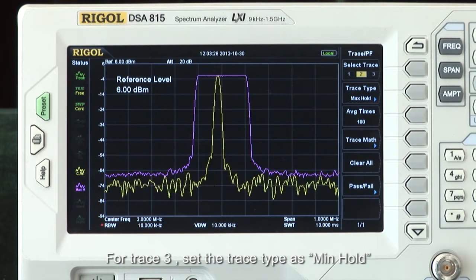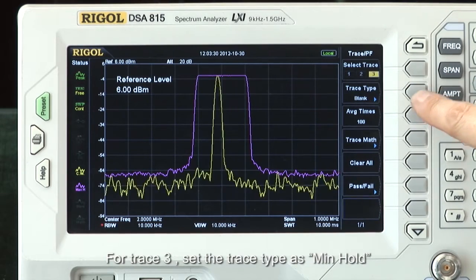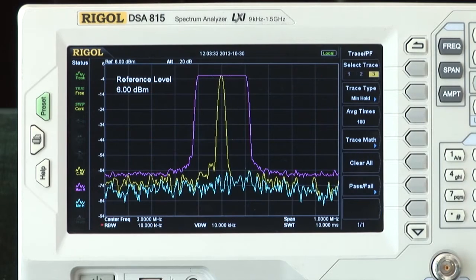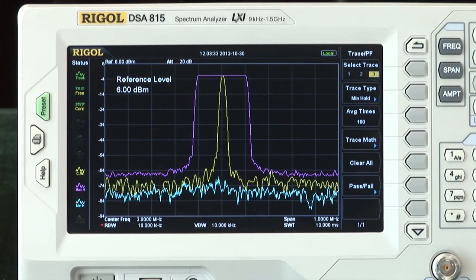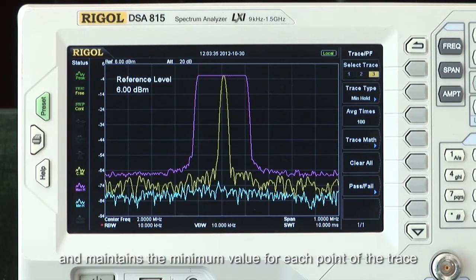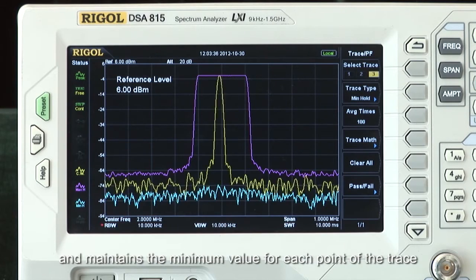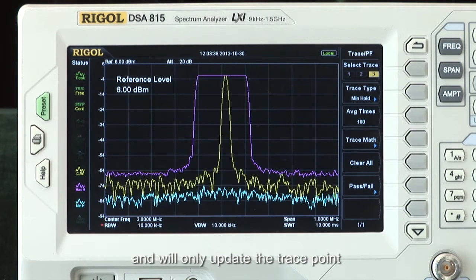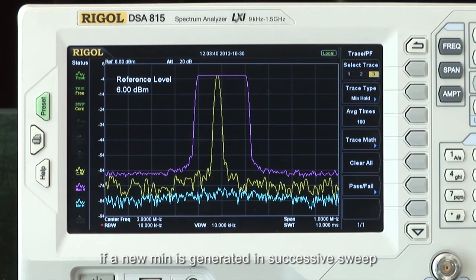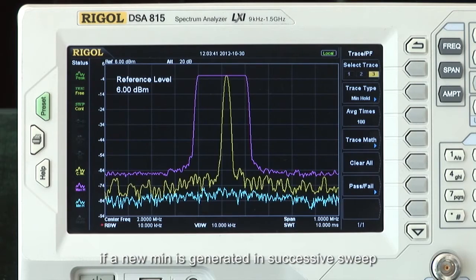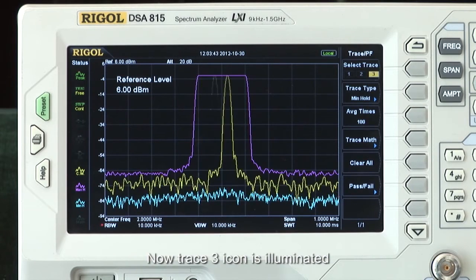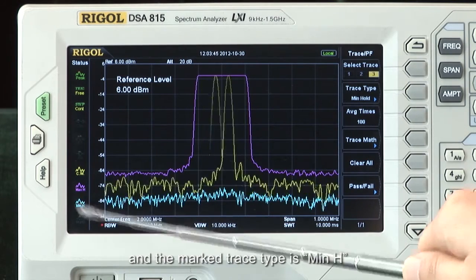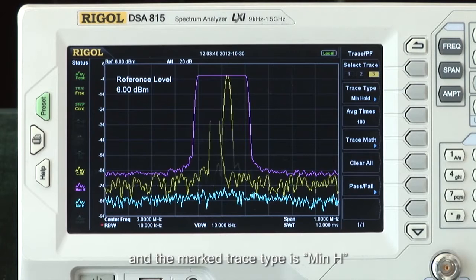For Trace 3, set the trace type to Min Hold. It is shown as a blue line and maintains the minimum value for each point of the trace, and will only update the trace point if a new minimum is generated in the successive sweep. Now the Trace 3 icon is illuminated and the marked trace type is Min H.